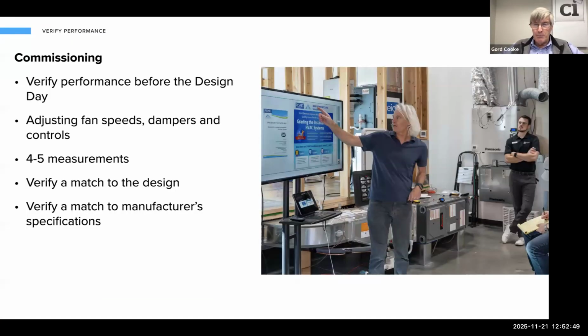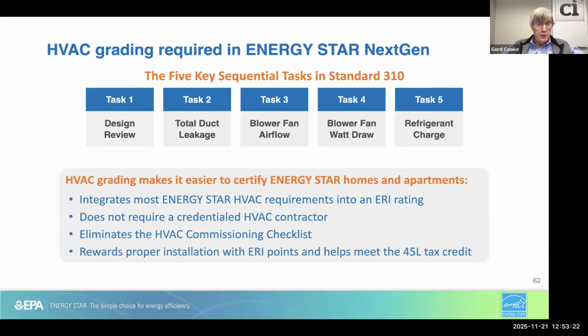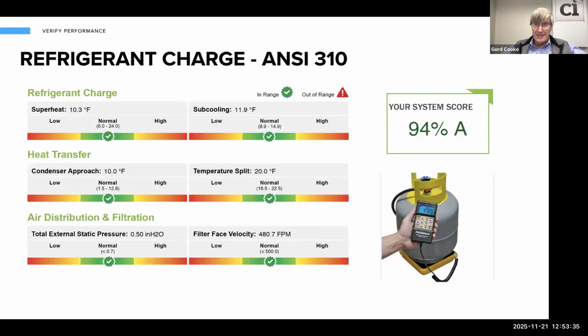Next on our list, I just want to mention the importance of verifying performance, because people are worried about the reliability. In today's world, we have technologies and standards that allow us to verify the performance. This is actually at our facility in Denver, where we're demonstrating the technology of what's called ANSI 310, the verification procedure, where you're adjusting speeds and dampers, you're taking 4 or 5 measurements, and you're verifying that the system is actually working to the manufacturer's specifications. It is a 5-step process where you do a design review, you understand duct leakage, you measure the blower fan, both its airflow and its watt draw, and you take a refrigerant charge, and it gives you a test performance for that system. There's the rating.